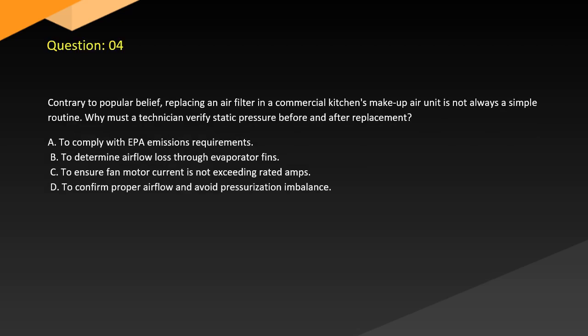Question 4. Contrary to popular belief, replacing an air filter in a commercial kitchen's makeup air unit is not always a simple routine. Why must a technician verify static pressure before and after replacement? A. To comply with EPA emissions requirements. B. To determine airflow loss through evaporator fins. C. To ensure fan motor current is not exceeding rated amps. D. To confirm proper airflow and avoid pressurization imbalance.